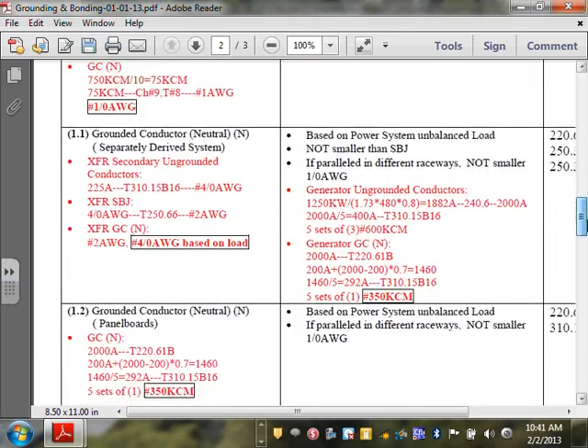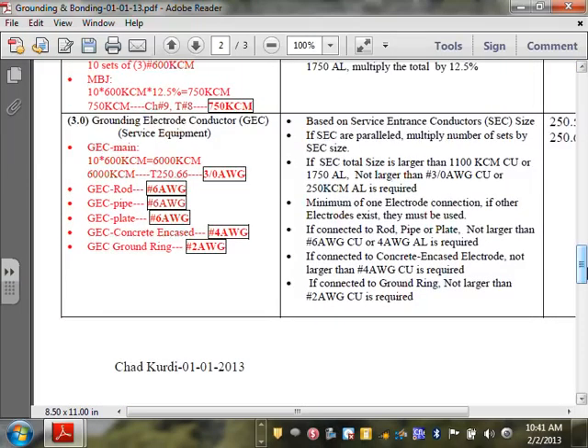Let me just go to 3, guys. So we have the main grounding electrode conductor. It doesn't have to be more than 3. Now go to the one that goes to the rod. The code says if you are tying directly to the rod, you don't have to go more than number 6, right? So the wire that goes from the rod to the ground bar does not have to be more than number 6. True? That's directly. Again, the words are 'does not have to be'; you can go higher than that. The one that's going to the pipe does not have to be more than number 6. The one that's going to the plate does not have to be more than number 6. The concrete encased electrode does not have to be more than number 4. Does not have to be.